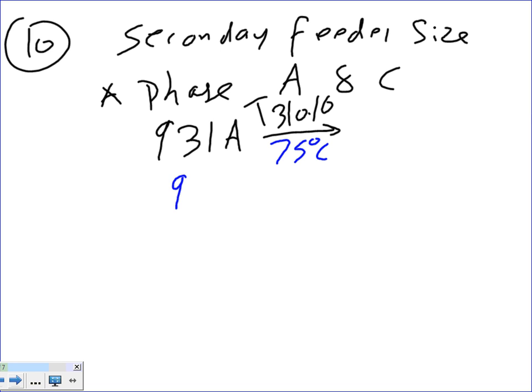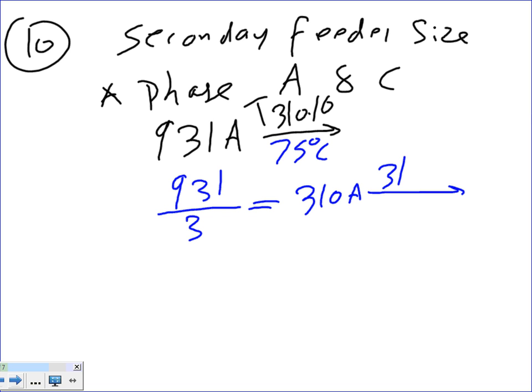So I take 931 divided by 3. Why did I pick 3? Because 3 gives me close to 300 amps, and 300 amps, guys, are good to carry with around 500 kcmil. If you divide this, you end up with 310 amps. Thank you. And if you take it to 310.16 table, under the 75-degree column, yes sir.